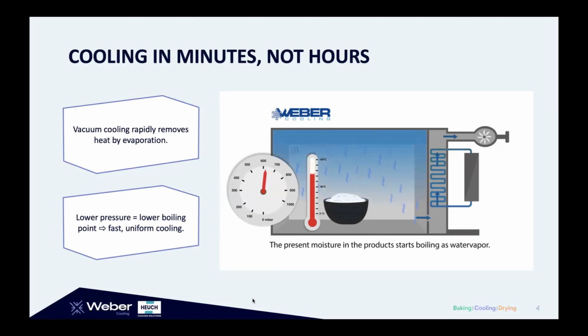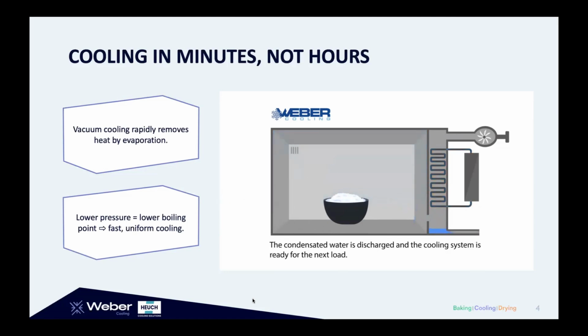If you continue to lower the pressure, because the vacuum pump continues to take out the air, you continue the process of evaporation and the cooling process. You can go all the way down to 6 millibar, which means 0 degrees, but you don't need that. So you stop at the temperature you desire, 40 degrees, 30 degrees, or you can even go down to 5 degrees.